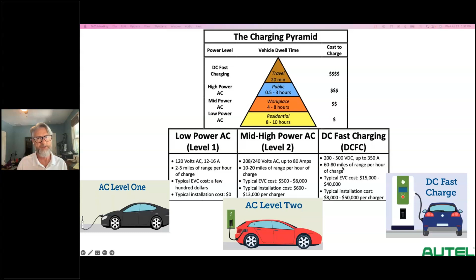From an installation viewpoint, we'll talk a little bit more about that later. These are 208 to 240 single phase, so a lot of existing businesses will be able to put these in because they already have those circuits in place, and sometimes we over-engineer, so there is opportunity there. This one is going to require 480, 3 phase, so you may have some significant infrastructure needed if you don't have that in place.